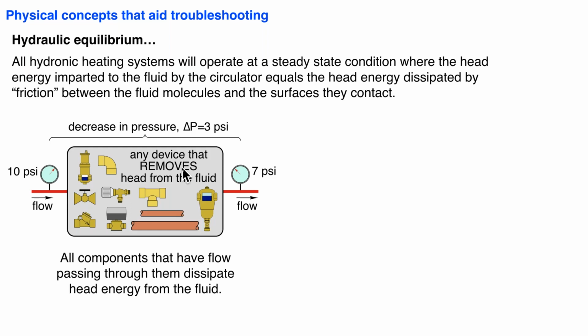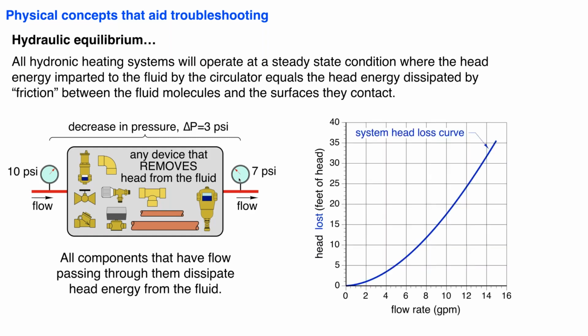The evidence of that dissipation is a drop in pressure. So for example, let's just say we have some collection of pipes and components in this gray box. We're going in at 10 PSI, we're coming out at 7 PSI. That drop in pressure, that delta P of 3 PSI, is the evidence that we have lost some of that head energy. And we represent that for a given hydronic system or circuit with what's called a system head loss curve. Now, if it's just a simple one loop system, the term system head loss curve is appropriate, but you could create a head loss curve for each zone circuit in a multi-zone system.